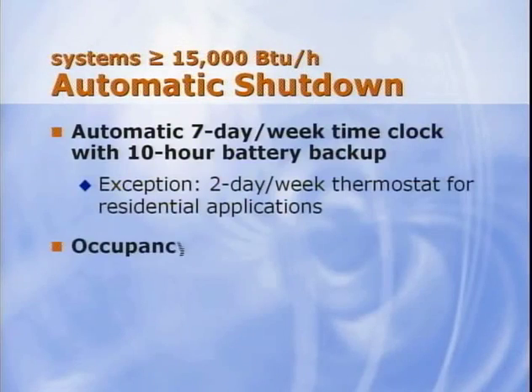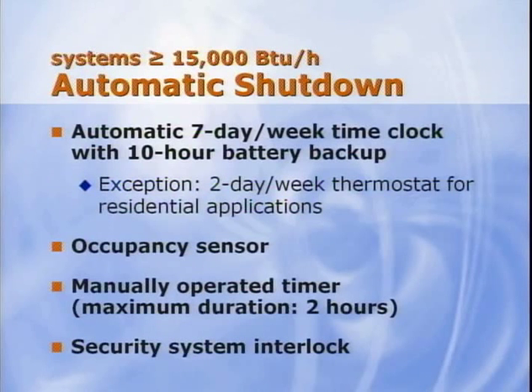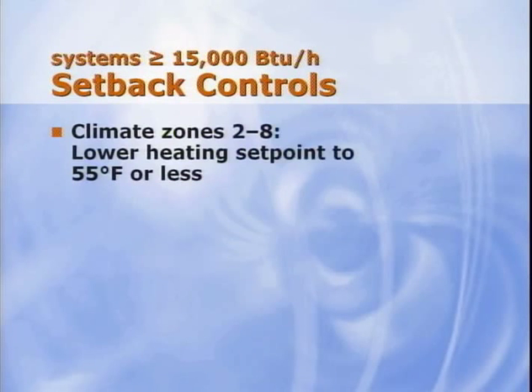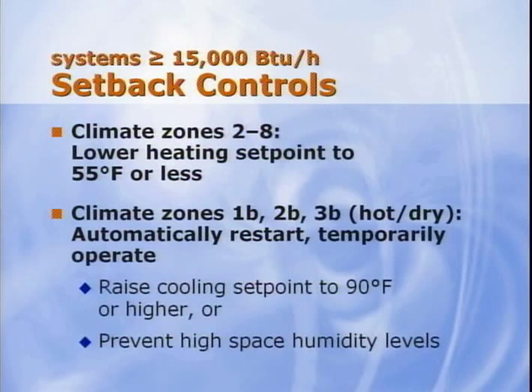Once the system exceeds 15,000 BTUH, a number of off-hour control requirements become applicable. The first is that automated shutdown is required so the system can be turned off without human intervention. Any of the 4 options shown on the screen satisfy this requirement. Temperatures are required to be set back. Heating setback is required in most climate zones. The exception is in the hottest climates. On the other hand, cooling setback is required only in hot, dry climate zones, but in those zones it must be automated.